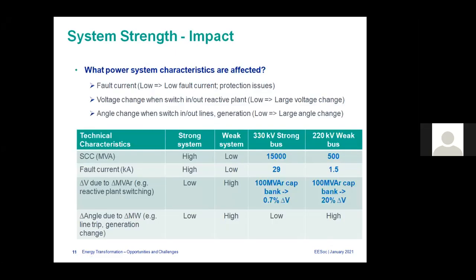And so why does this system strength matter? As I mentioned earlier, there are a few issues from a physics point of view, or when you operate the power system. One is, the lower the system strength, that means effectively lower fault current, so there can be protection issues. And not only that, you might have already come across this: if you have a high fault level or high system strength location, when you switch in or switch out reactive plant, the voltage change is much less compared to a weak fault level location.